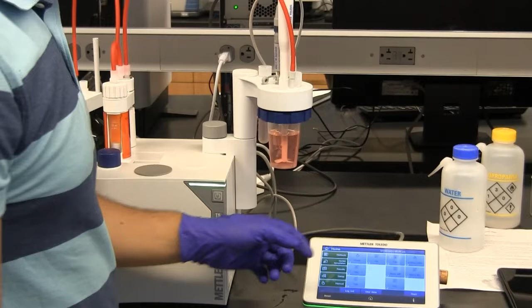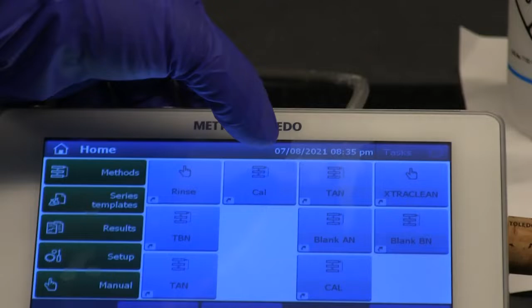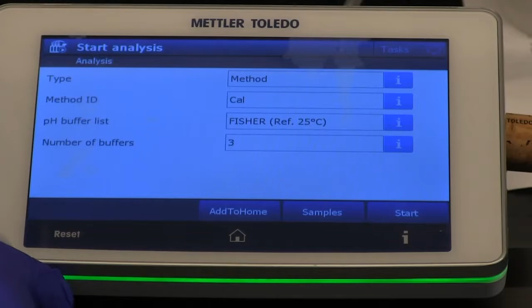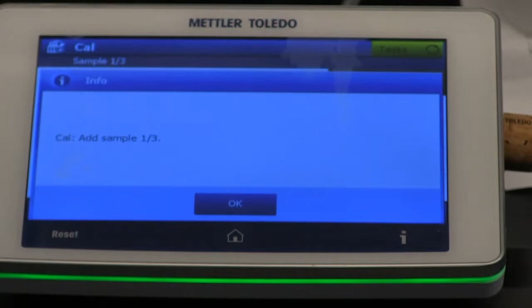And then on the screen you will have a cal option. You have two cals actually, so we'll keep using the one on the top. This is the right method. So press calibration, and then it will ask you for the number of buffers. You have 3 buffers, so you can just start. It will tell you to add the first sample. You already added it, so just click OK and wait. After it finishes the first sample, you remove this cup and bring another cup with the second sample, and in between samples you have to clean it with DI water.